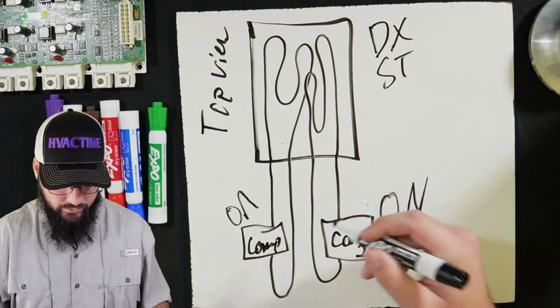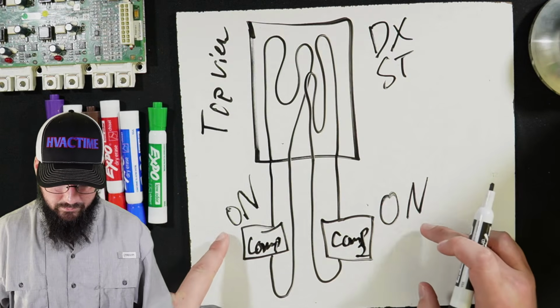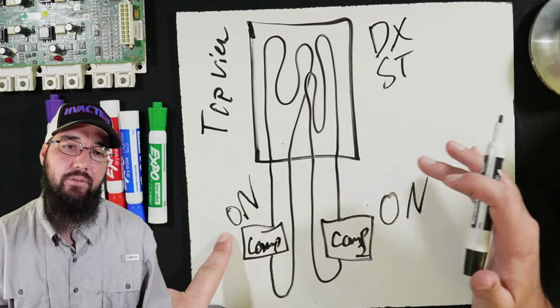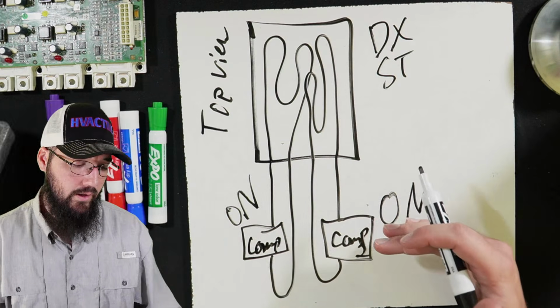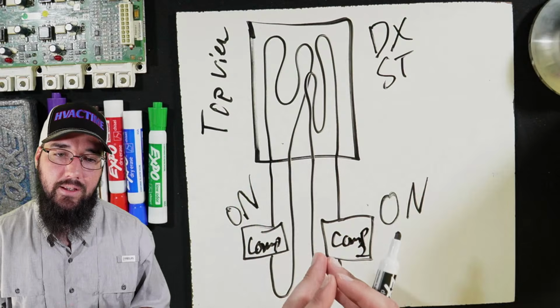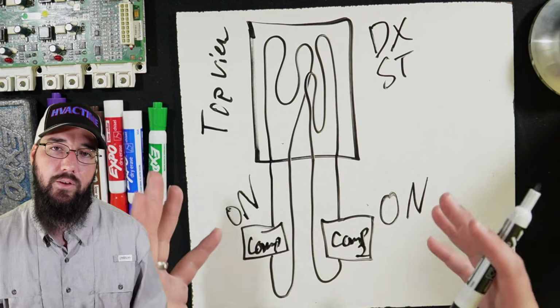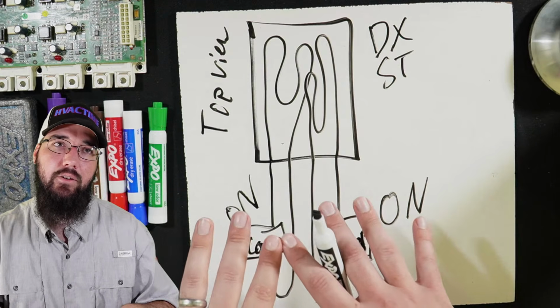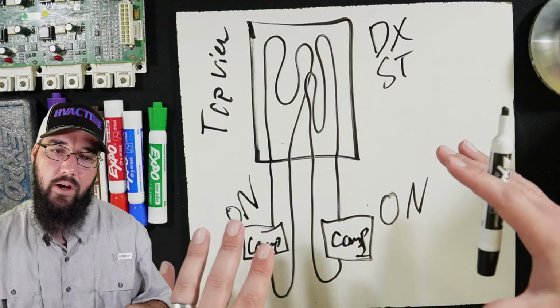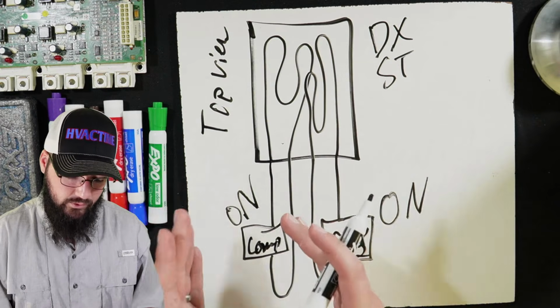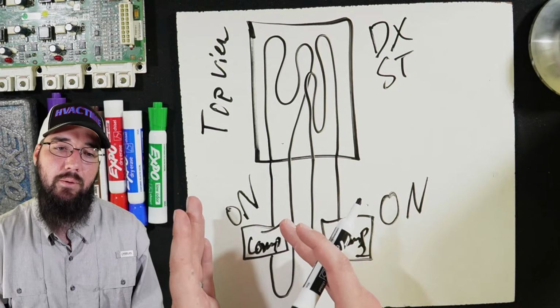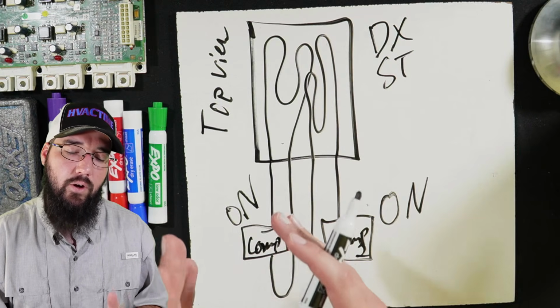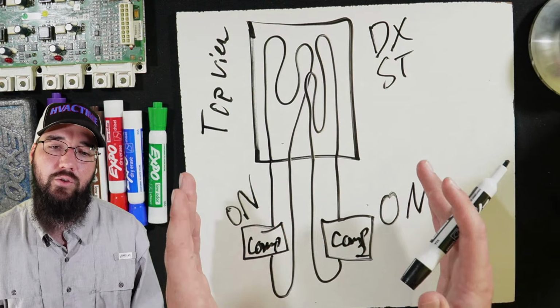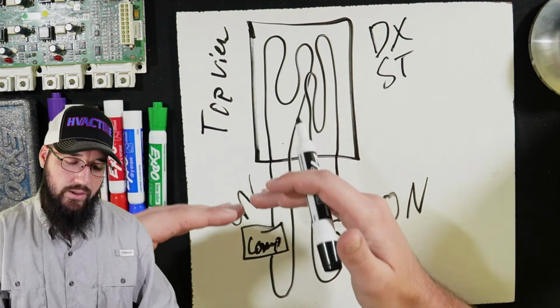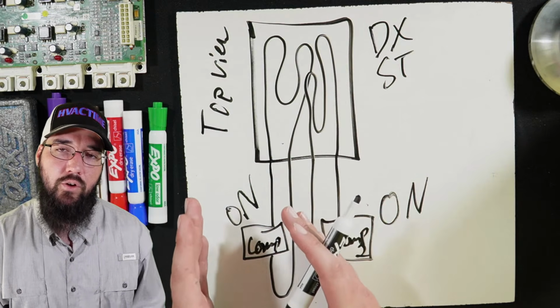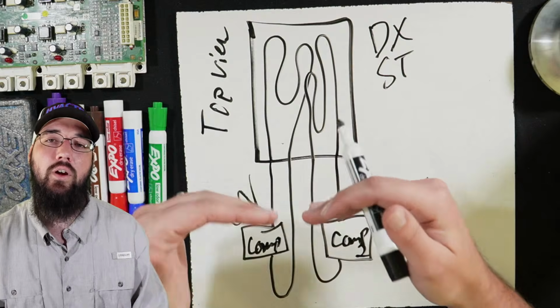Then when the second one turns on, now both of these are having to share that evaporator. That means all the heat in that evaporator is having to be split and shared between the two circuits, and this ultimately creates a higher approach value on each circuit. So both circuits, and specifically compressor 1, we had an example of its approach by itself, but now we've got circuit 2 involved, and it starts staging at the exact same staging points it had a moment ago by itself. You're going to see a higher approach value in total.